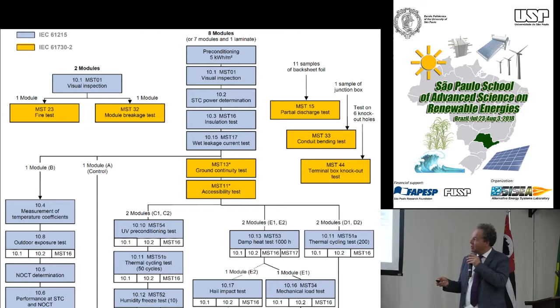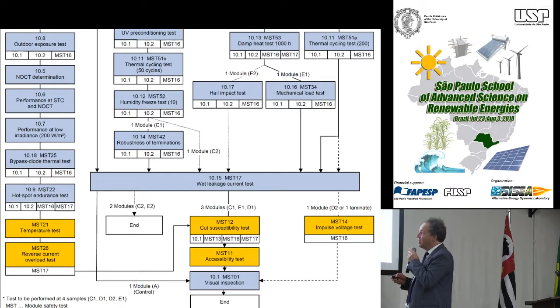Coming to the second part, these are the other parts of the thermal cycling and then robustness of terminations. Here you see the bypass diode tests, to see whether the bypass diode is strong enough to survive even a load which is 25% higher than normal load. Then the hotspot endurance test: if you shadow one cell, you see whether it causes such a high temperature that the cell will burn.